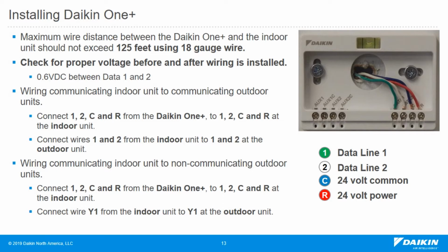When working on one of these systems, keep in mind the data 1 and 2 is our data communication, and we'll look for 0.6 volts DC between 1 and 2. And from 1 to common and 2 to common, we should exceed 2.0 volts DC. If we're getting below 2.0, we may have to turn some data filters off. Please reference the installation and service portion, or give us a call and we'll walk you through it.